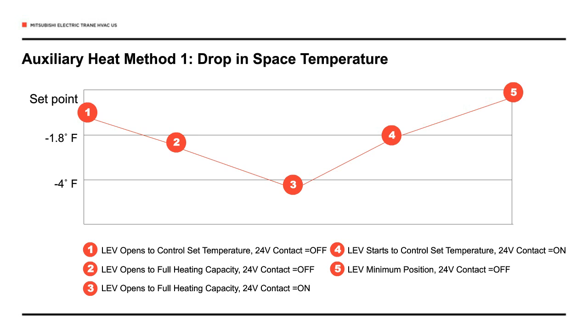So at point 3 in this example, at 4 degrees below our set point, we're engaging the auxiliary heat, and then the temperature starts coming up, and we get all the way back to point 4 and then point 5, where we turn the auxiliary heat off and then just rely on the VRF heat pump heat at that point. So that's our space-by-space method.